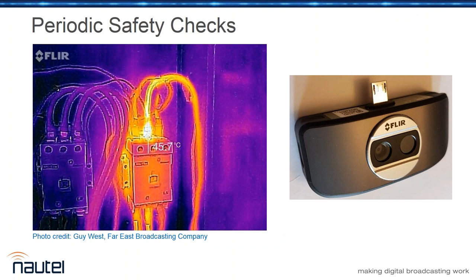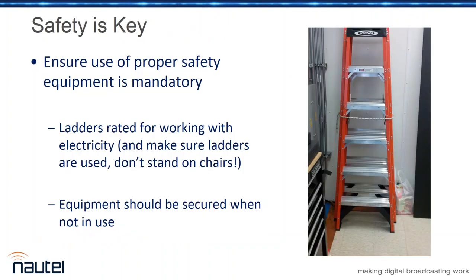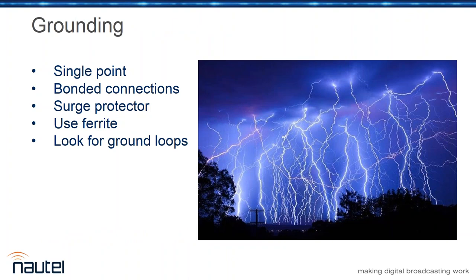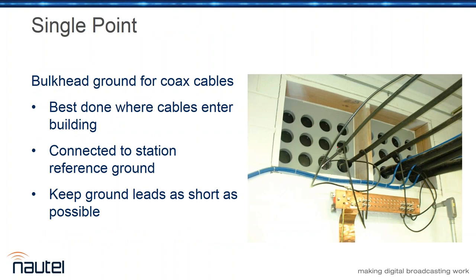John had noticed in a slide that a ferrite was located right at the entrance bulkhead. Where the ferrite is located is less important, less critical. What I find more important is that the ferrite, in this case, looks like it's actually before, assuming it is a ferrite, and that wouldn't be as good. I'd rather see the ferrite on this side of the ground kit. Putting it over there just adds an impedance and makes it harder for lightning energy to get to ground. So definitely in this particular picture, that'd be another case of what's wrong with this picture. You want the ferrite on the load side.